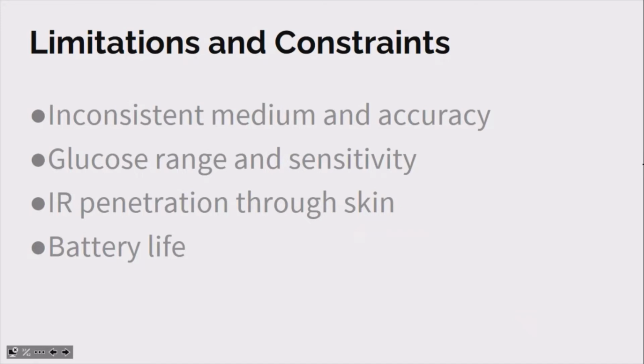And also the sensitivity, as our device falls well within the standard, but we're not accurate to the nearest digit in particular. And then we have IR penetration through the skin. The tests that we performed were done with just blood in the well plate, which does not reflect how it would actually be used day to day. If this was to be used through skin, it would likely need much stronger IR lights than we used for our experiments. And then the stronger lights would end up using much more power, which presents a potential issue with the device's battery life.